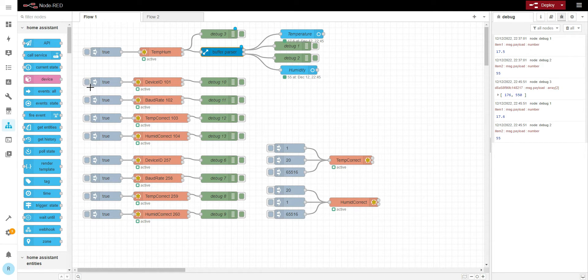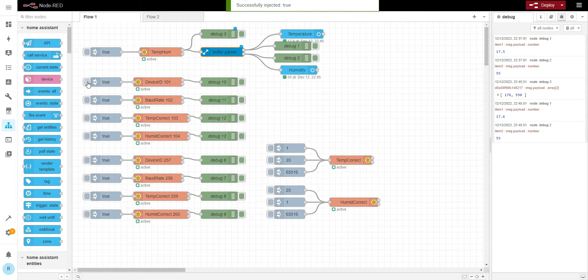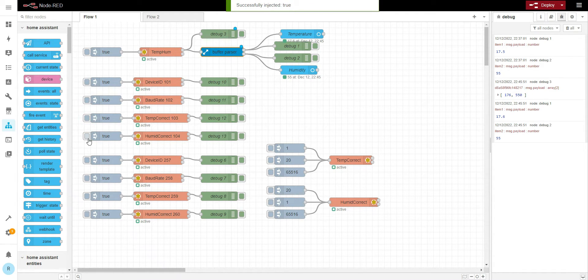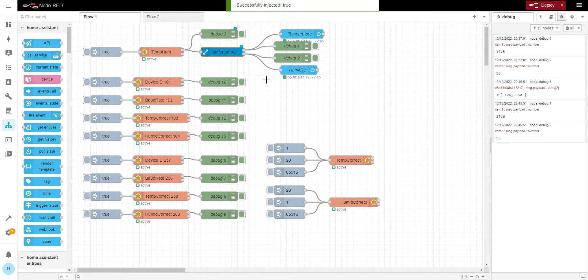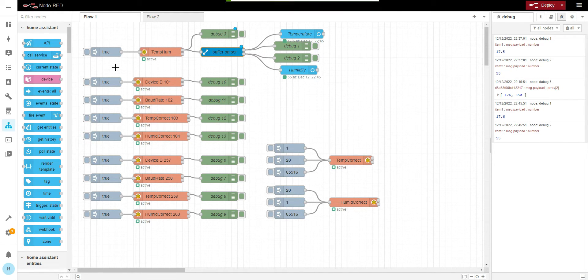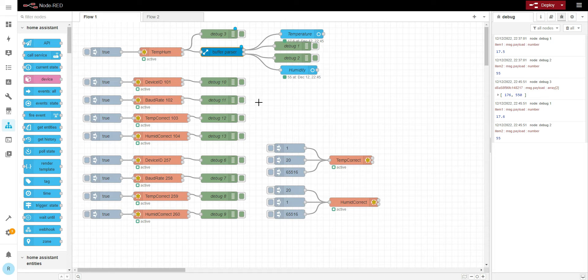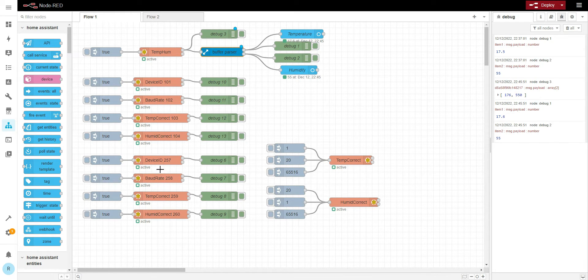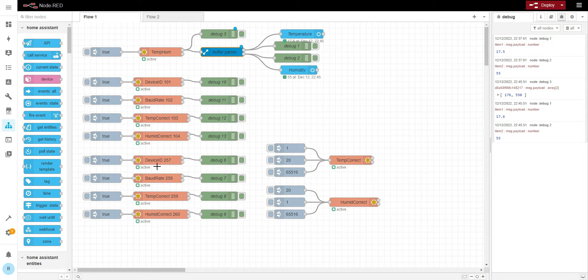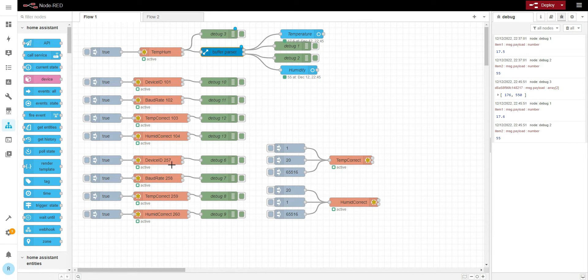But if we try to read these registers, nothing happened. They basically don't exist. Basically this Modbus map, what I found online, is not exactly correct. So I did more research and I found on YouTube one guy was changing the device address on this unit, and he used register 257.